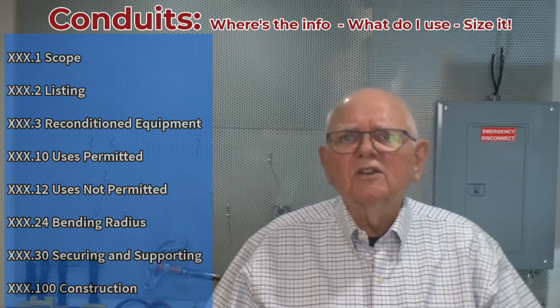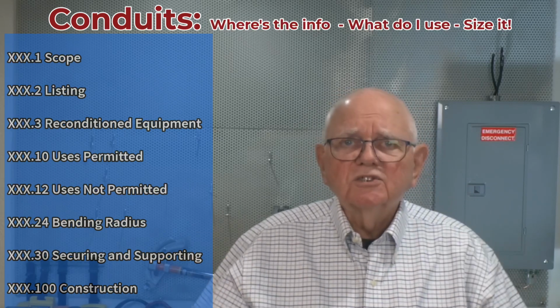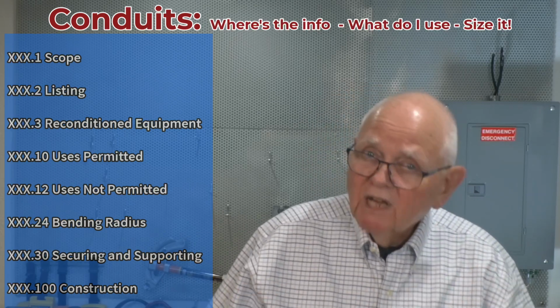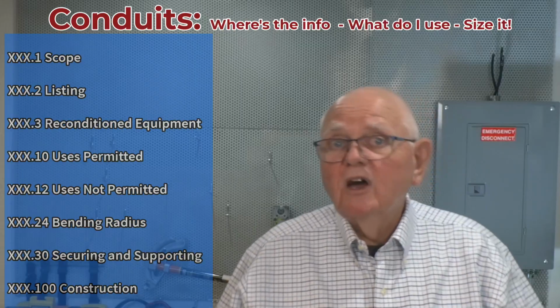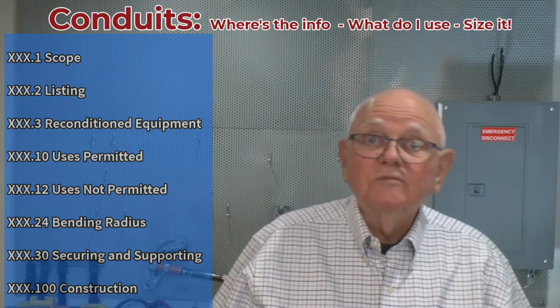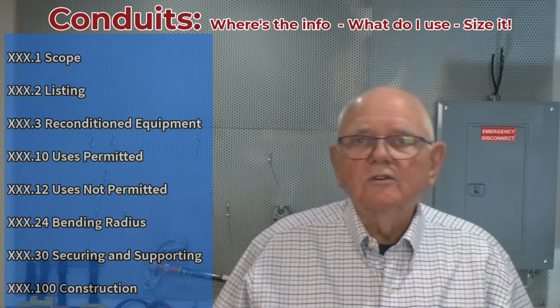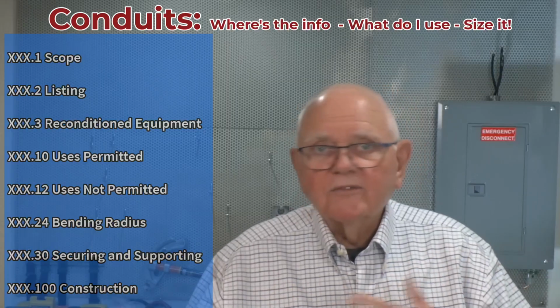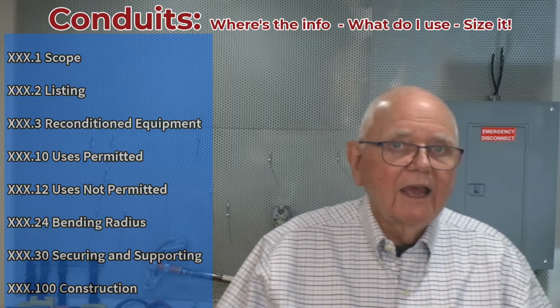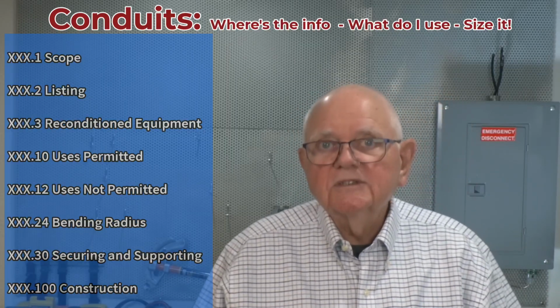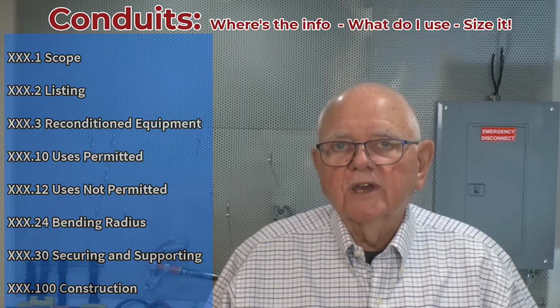Rigid, where I have to cut it and thread it and ream it and so on and so forth, and it's not easy to bend, it's going to take me longer to install than EMT or fiberglass conduit or something like that. So anyway, but if I'm in a hazardous location, hey, I have to use that type of conduit that's suitable for hazardous location then.